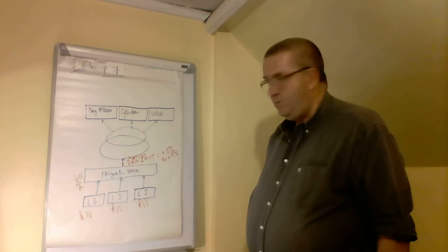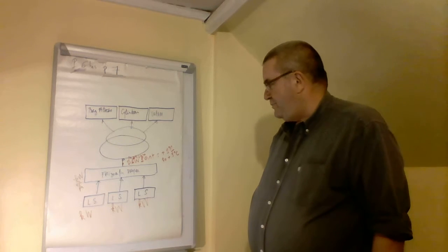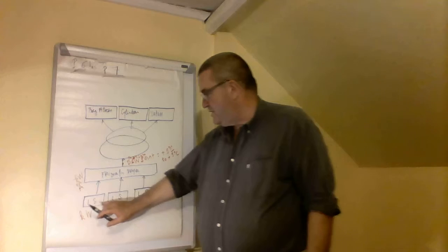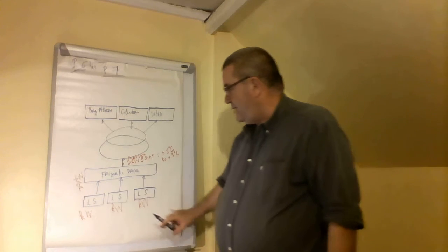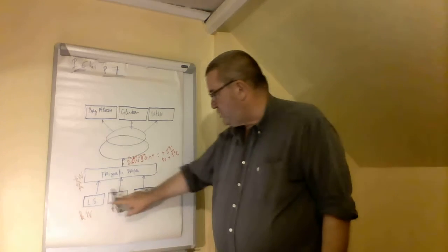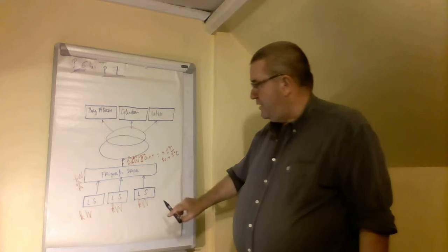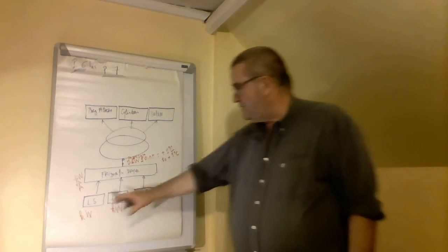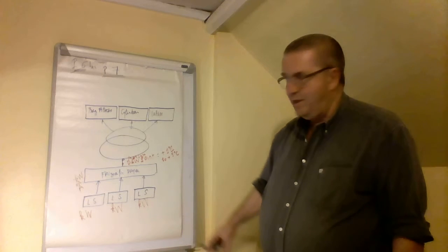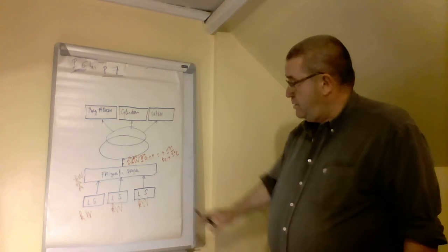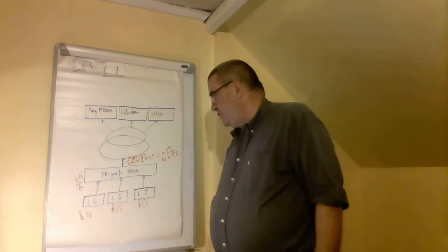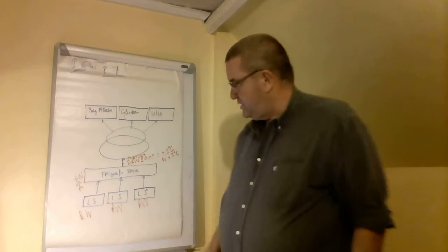It's a small machine. Normally it's only a part of it. If you have 100 kilowatt here, maybe the dryer on each of the compressors might possibly be 10. You have 3 compressors of 300 kilowatt that can run together, and you will choose a frigorific dryer, if it is 7 bar air, around 10 kilowatts.